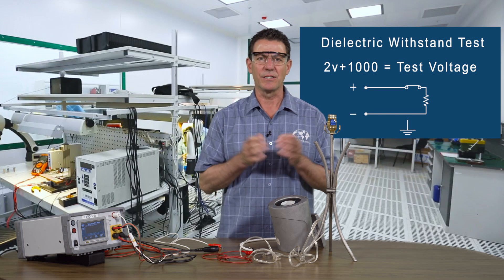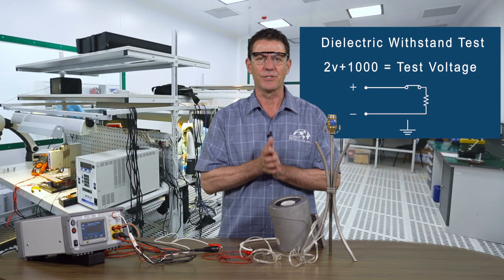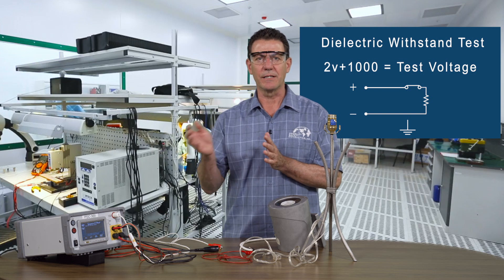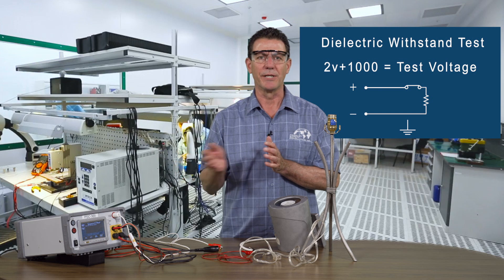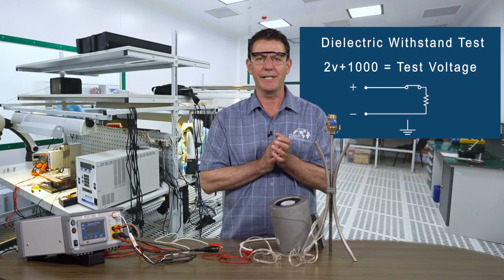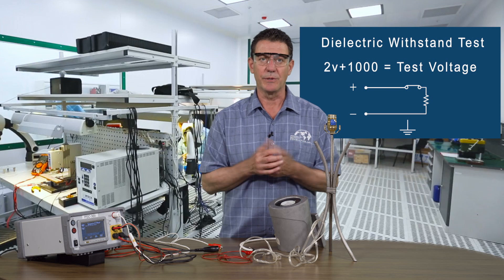The test is a test of the insulation system of the product. We want to make sure no wires are nicked that are touching accessible metal parts. We want to make sure spacing between live parts is adequate and that is why we do this test.